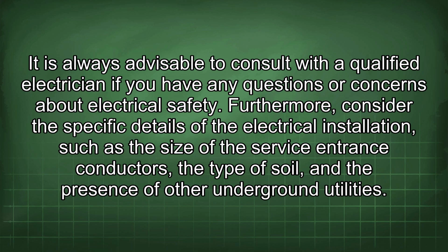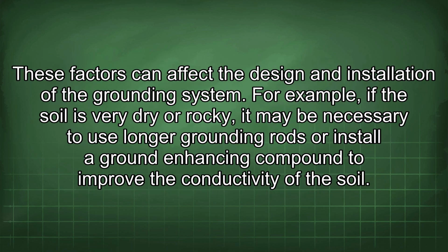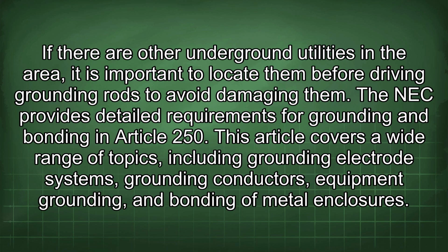Furthermore, consider the specific details of the electrical installation, such as the size of the service entrance conductors, the type of soil, and the presence of other underground utilities. These factors can affect the design and installation of the grounding system. For example, if the soil is very dry or rocky, it may be necessary to use longer grounding rods or install a ground-enhancing compound to improve the conductivity of the soil. If there are other underground utilities in the area, it is important to locate them before driving grounding rods to avoid damaging them.